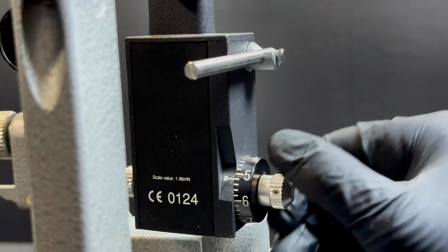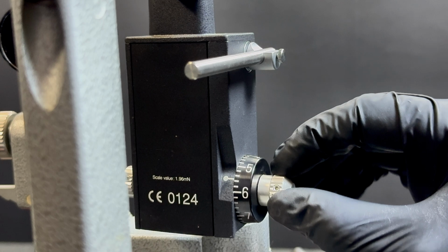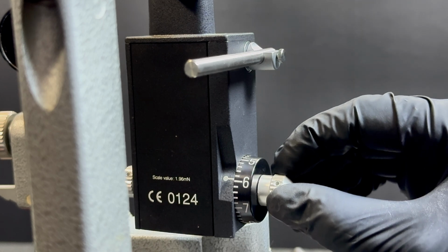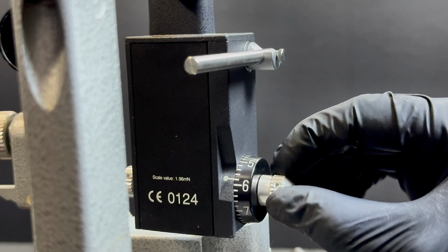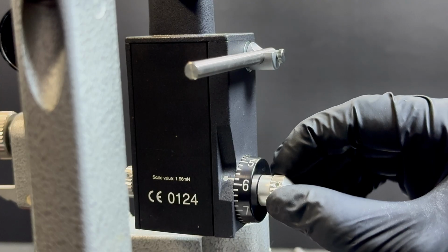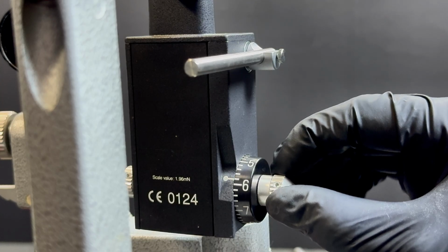This example shows a tonometer out of calibration at the 6th setting with an early drop. The test bar detents before reaching 6 and returns to neutral near 5.6, indicating improper calibration.